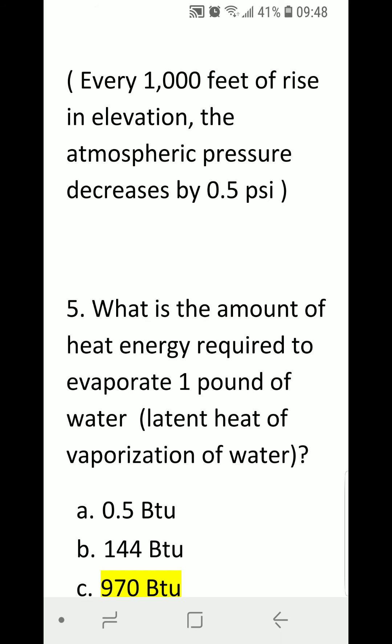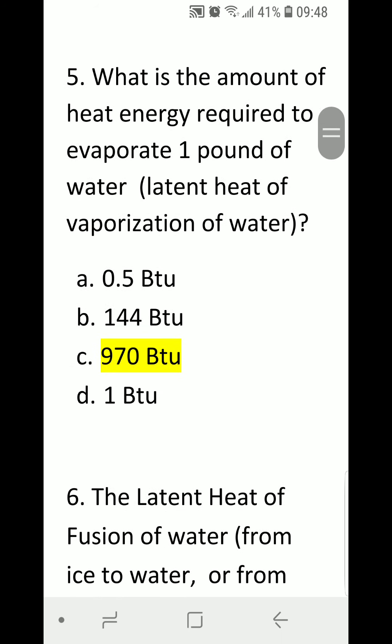Number five: What is the amount of heat energy required to evaporate 1 pound of water, the latent heat of vaporization? A) 0.5 BTU, B) 144 BTU, C) 970 BTU, or D) 1 BTU. The correct answer is C, 970 BTU. For every pound, you need 970 BTU of heat to evaporate or vaporize water.